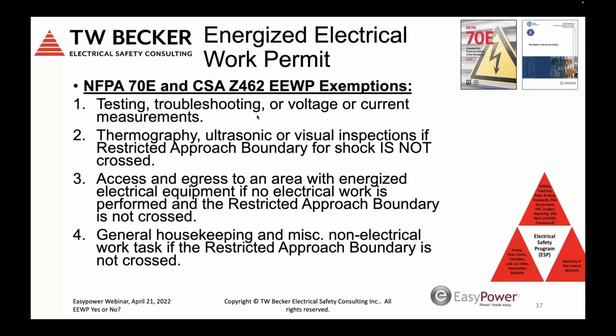Now the next exemption, item 2, says thermography, ultrasonic or visual inspections if the restricted approach boundary for shock is not crossed. So it's saying, well, we can have the equipment open, a door is open, hinged, or a bolt on cover removed. Those are separate work tasks. But the work task of using a thermographic camera, an ultrasonic test instrument, or doing visual inspections, we don't need a permit for that. But it doesn't say that opening the hinge door or removing the bolt on cover is exempted. And I'm going to talk about that because I believe we do need exemptions for those two work tasks.